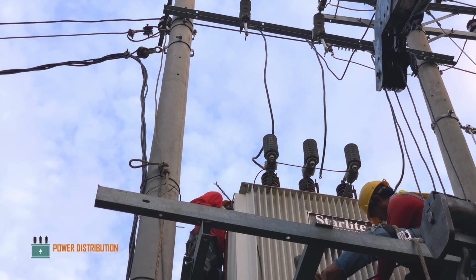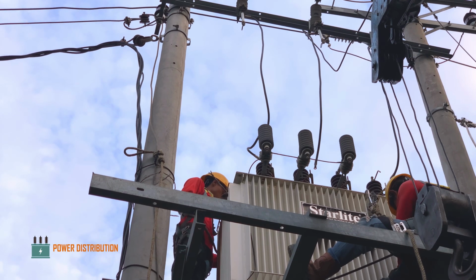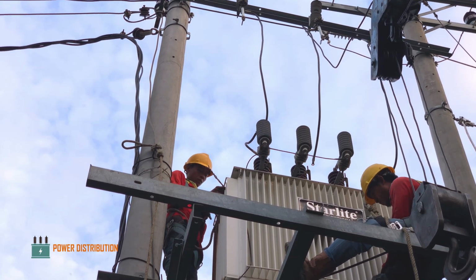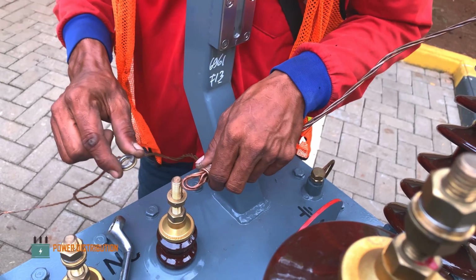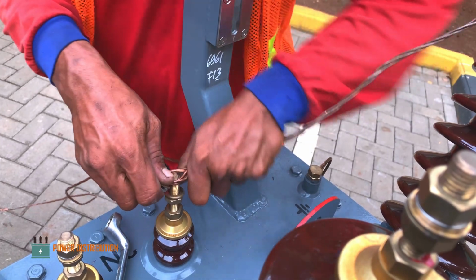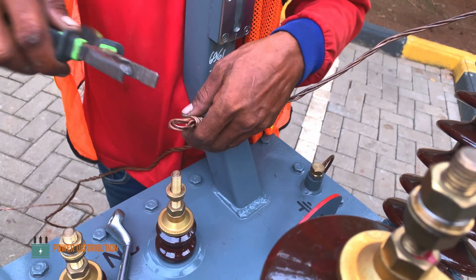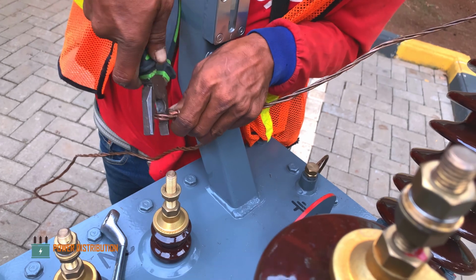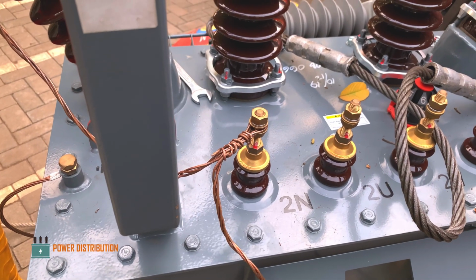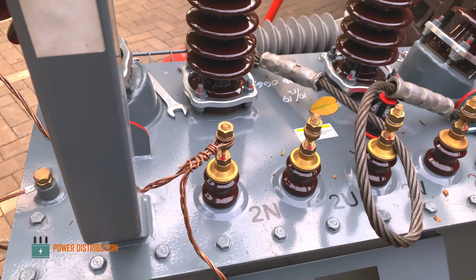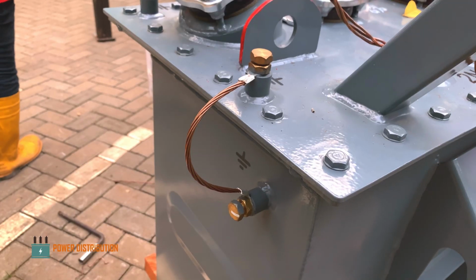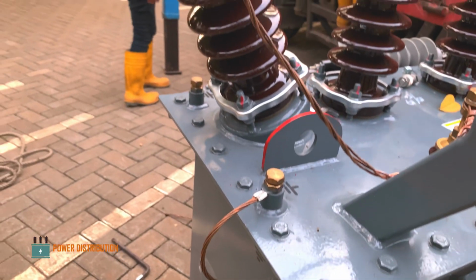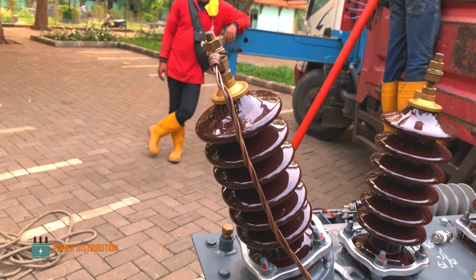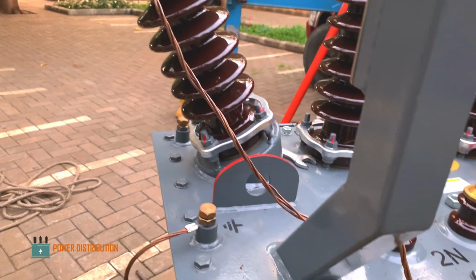Then the crew installed the grounding system to the body of the transformer, starting from the secondary bushings. It's established between the secondary bushings, primary bushing, the body, and down to the grounding terminal at the bottom of the transformer. In this transformer, we are using a 25mm bare copper conductor as the grounding wire.